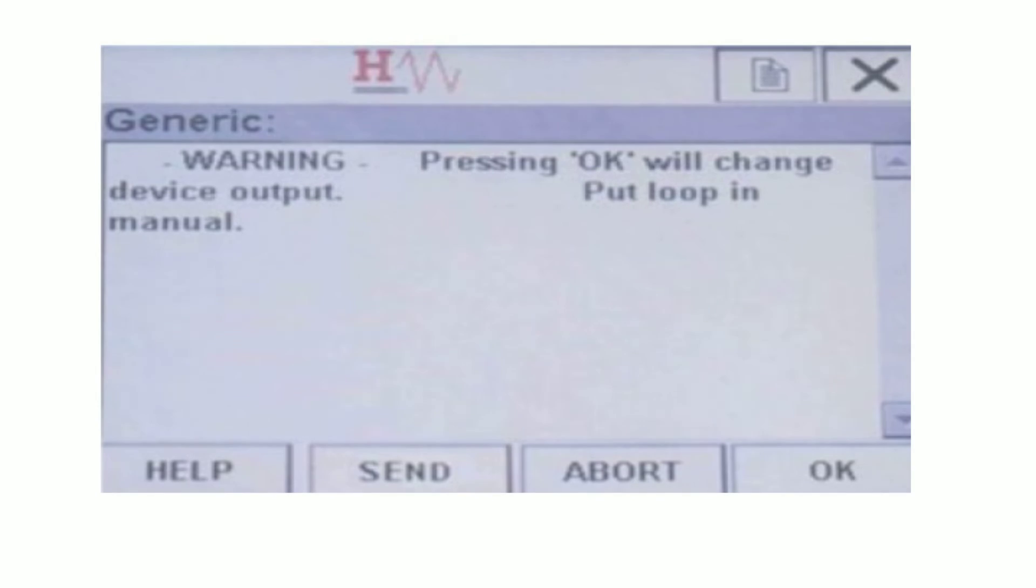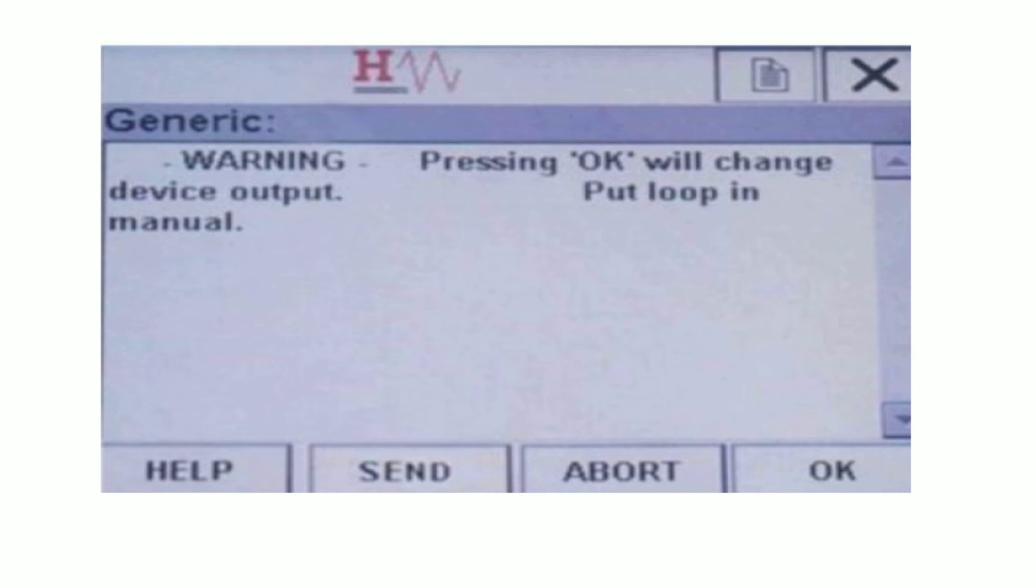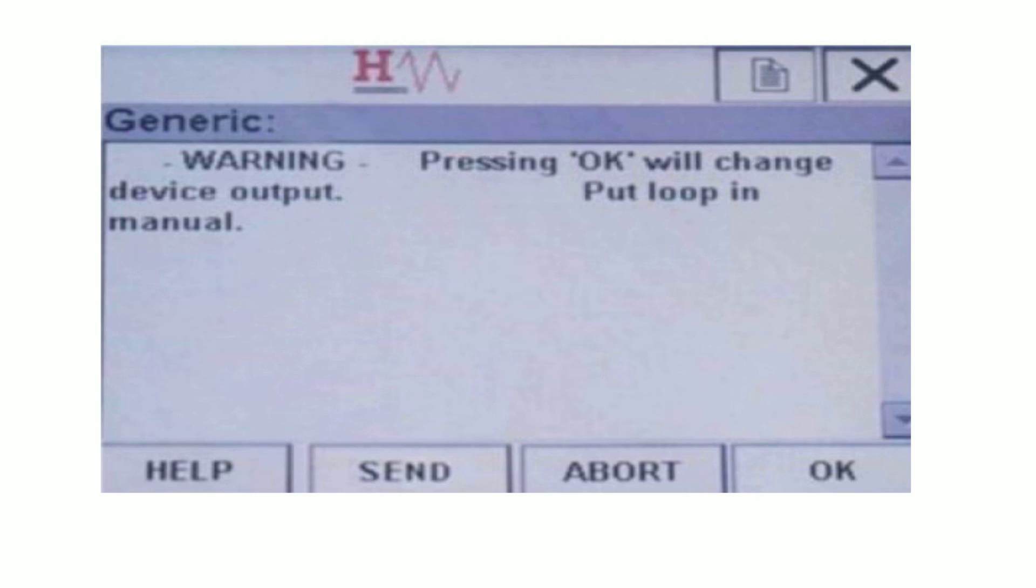After a calibration value has been changed on the 475 communicator, the change must be sent to the smart device to take effect. So tap the Send, which will write the new value in the device. So this is the simple and easy way to perform 4 to 20 milliampere's calibration of smart transmitter by using HART Communicator.